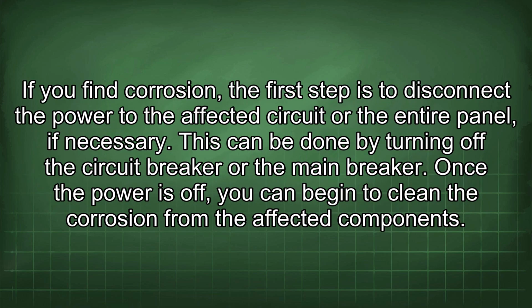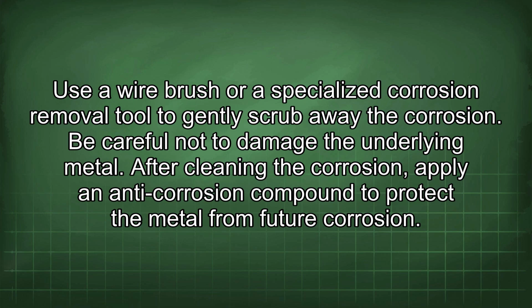If you find corrosion, the first step is to disconnect the power to the affected circuit or the entire panel if necessary. This can be done by turning off the circuit breaker or the main breaker. Once the power is off, you can begin to clean the corrosion from the affected component. Use a wire brush or a specialized corrosion removal tool to gently scrub away the corrosion. Be careful not to damage the underlying metal.